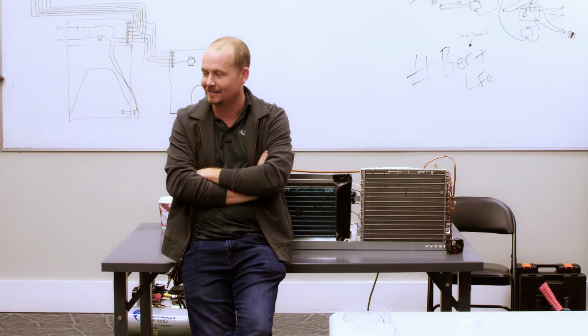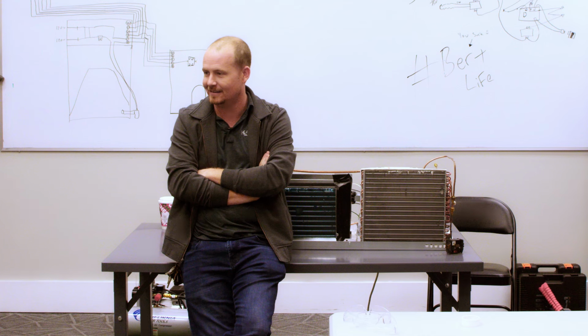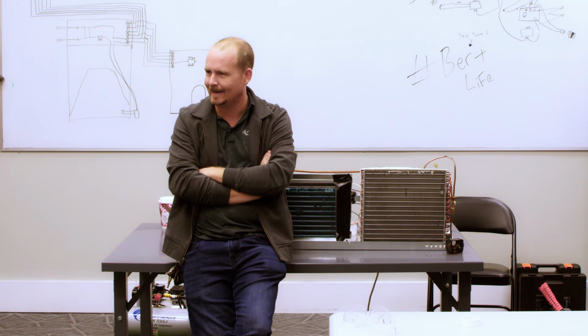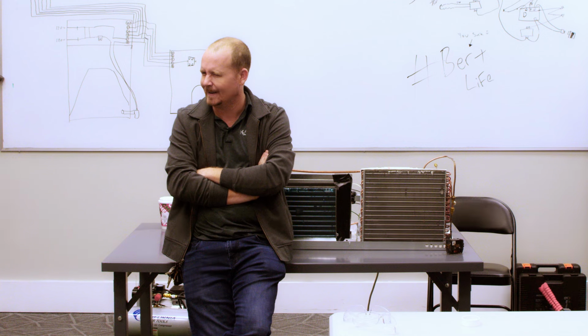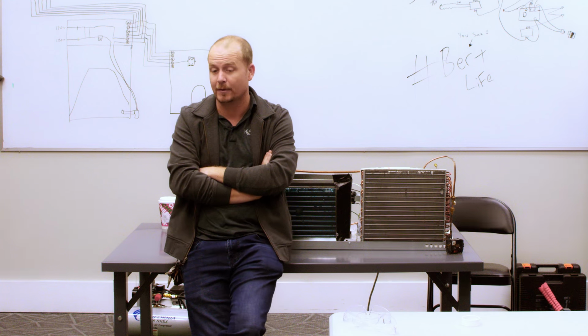The good stuff in the manual about piping lengths, so you just have to do it till you hit subcool. It doesn't say, hey, add this much refrigerant, not in Carrier. Sure. Unless it's a Carrier ductless system. The ductless system is different. Yeah. So I think you bring up a good point.